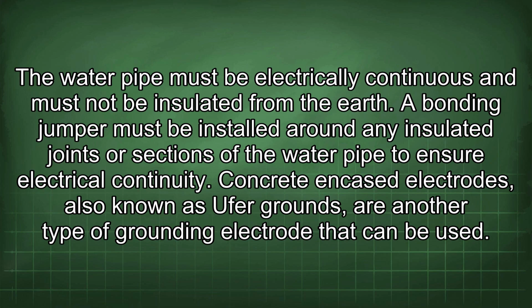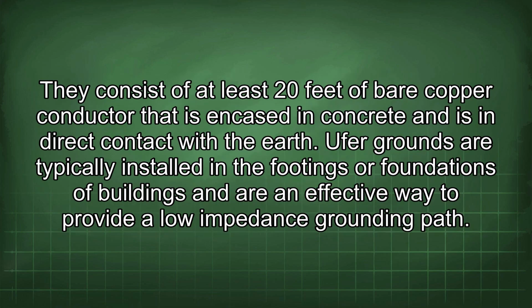Concrete encased electrodes, also known as Ufer grounds, are another type of grounding electrode that can be used. They consist of at least 20 feet of bare copper conductor that is encased in concrete and is in direct contact with the earth. Ufer grounds are typically installed in the footings or foundations of buildings and are an effective way to provide a low impedance grounding path.